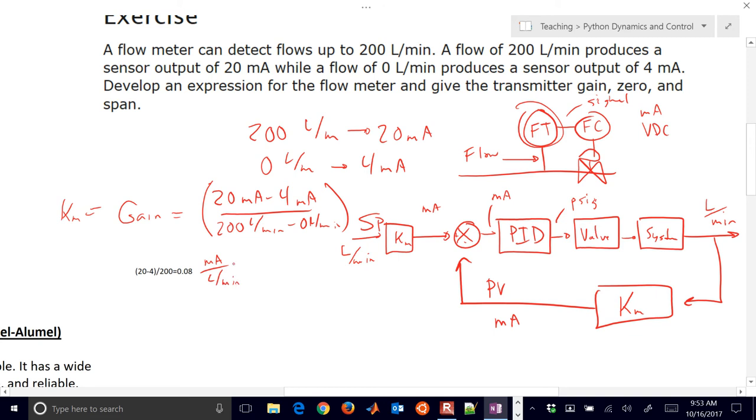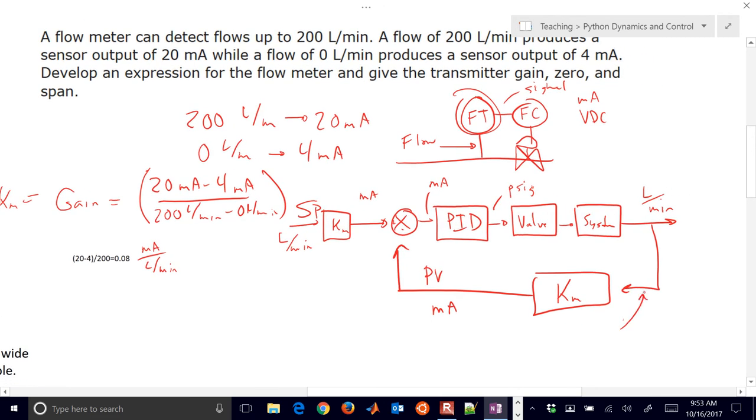So I'm going to take whatever signal I had here, and I'm going to multiply it by that gain, and it's going to produce a milliamp signal. And also the same thing with my set point right here. It's also going to produce a set point that's in milliamps. And then I'm going to compare them there, and that's going to be the input to my PID controller.